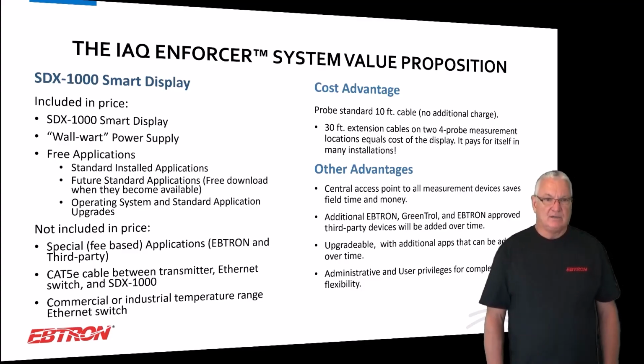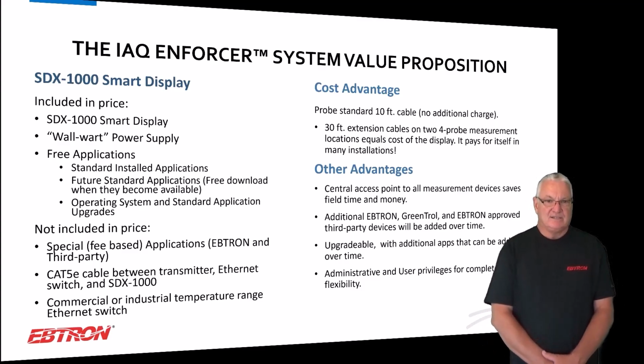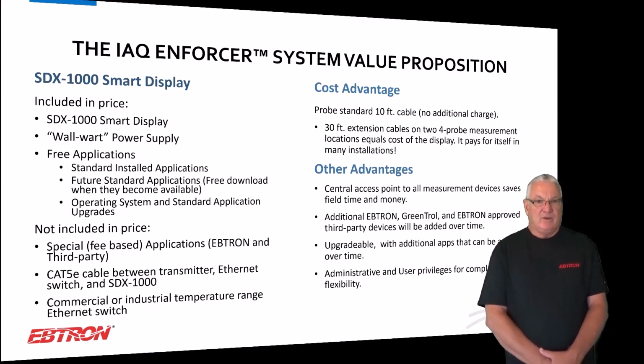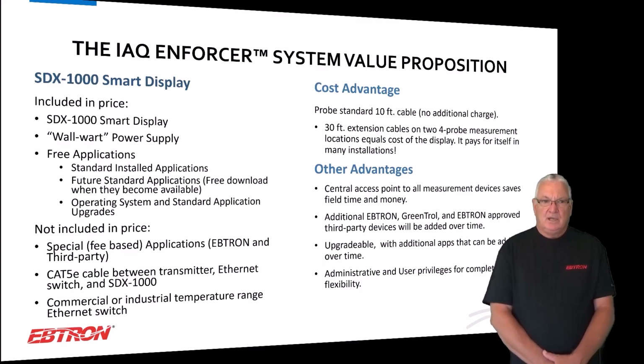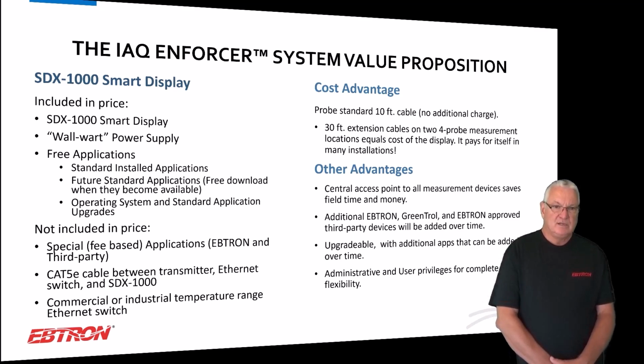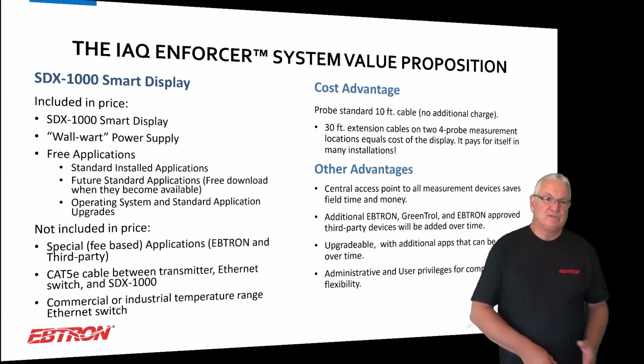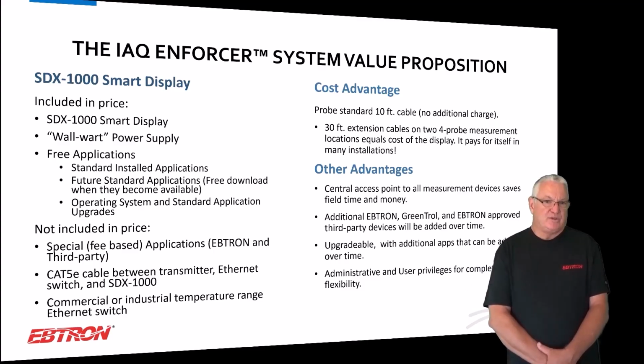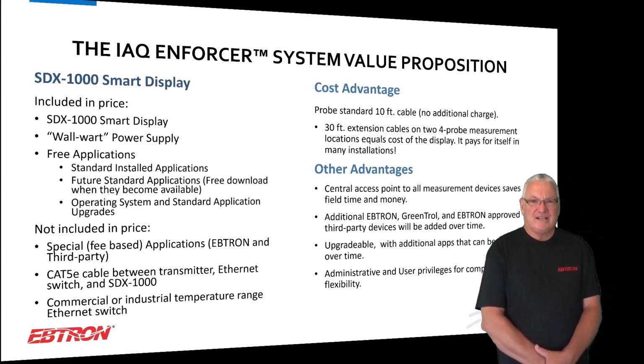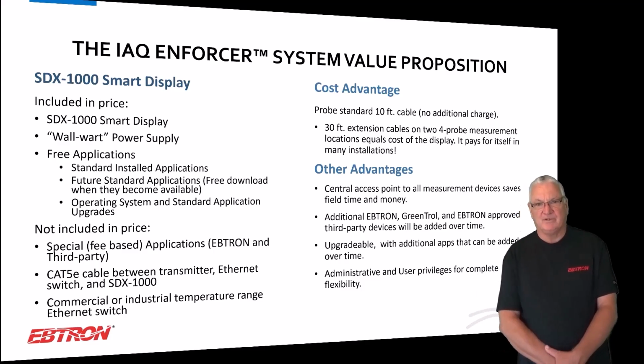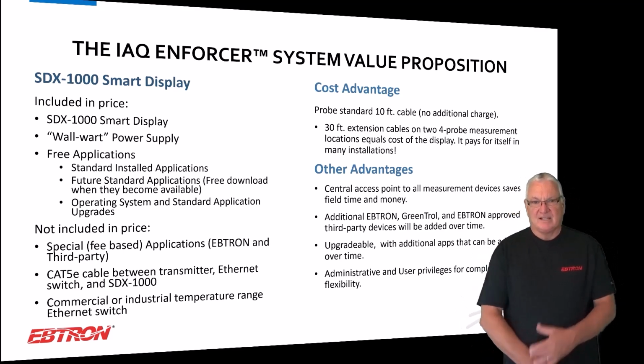What's not included? Well, there could be fee-based applications someday, but there isn't right now. And we don't provide the Cat5e or higher cable, and we do not typically provide the Ethernet switch. We do have the ability for you to purchase an industrial Ethernet switch from us, but we don't make it, so we can also give you the specs on that if you prefer. Some people want a package, some people just want to go ahead and get it. Commercial switches work fine. Just remember, commercial residential switches are just that, residential switches. The cost advantage, I kind of said already: 30-foot extension cables on 2 4-probe measurement locations equals the cost of the display. And it's got lots of advantages.